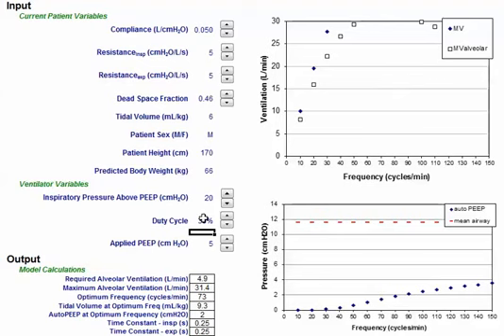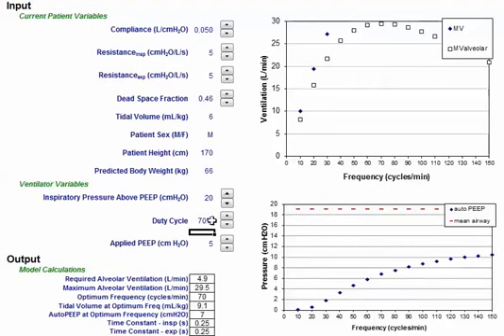I'm going to change this to 50% or 1 to 1. As you can see, I'm attaining my max minute ventilation obtainable. And then if I made this an inverse ratio — increased it to 60% or even 70% — it's going to drop my minute ventilation.